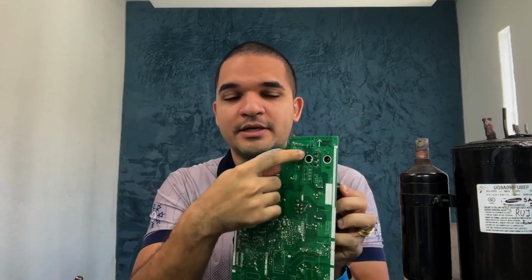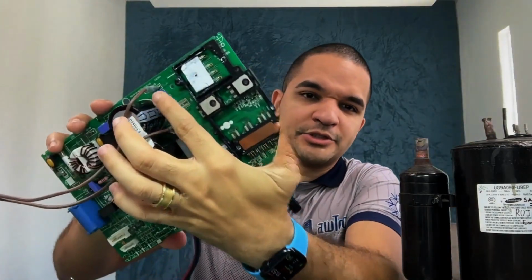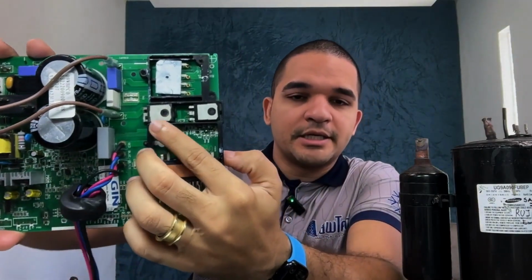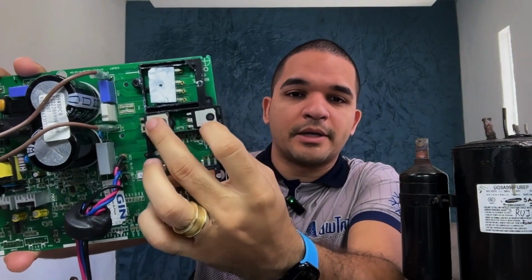If the rectifier bridge is beeping, whether it's in this model here, look, this Elgin model, here's the rectifier bridge. See, it's covered in thermal paste. If there's an IGBT, you're going to measure the IGBT, you're going to measure the power diode. You check continuity on all the components that are on the power heatsink. There you go. That's the master tip. Measure the continuity of all the components that are on the power heatsink.